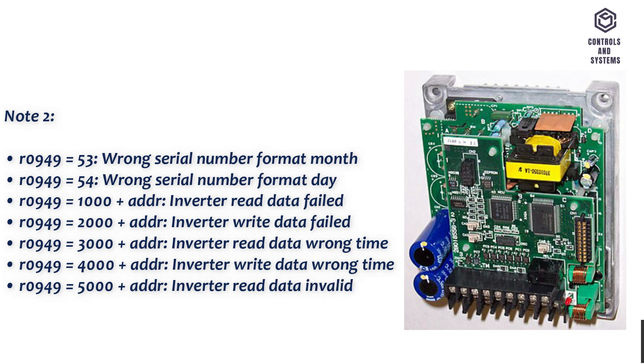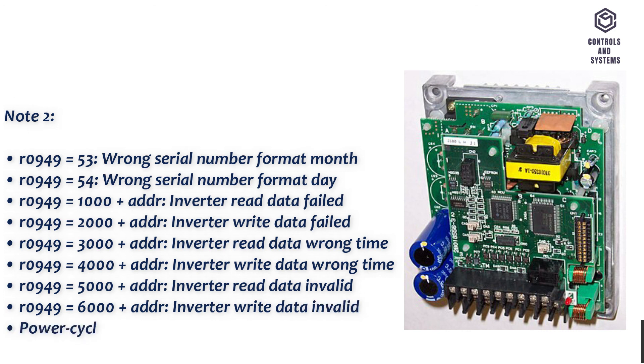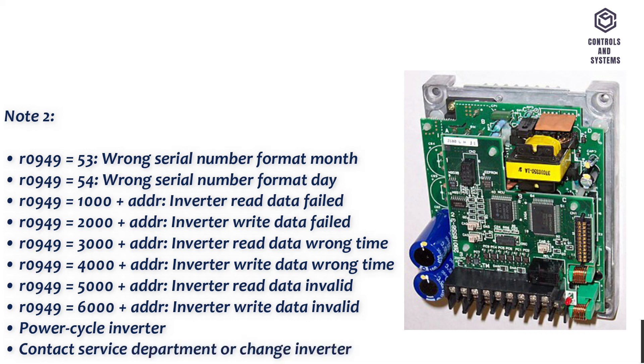R0949 equals 4000 plus address: inverter write data wrong time. R0949 equals 5000 plus address: inverter read data invalid. R0949 equals 6000 plus address: inverter write data invalid. Power cycle the inverter. Contact the service department or change the inverter.